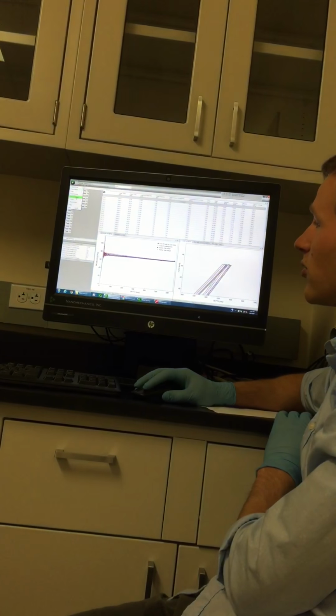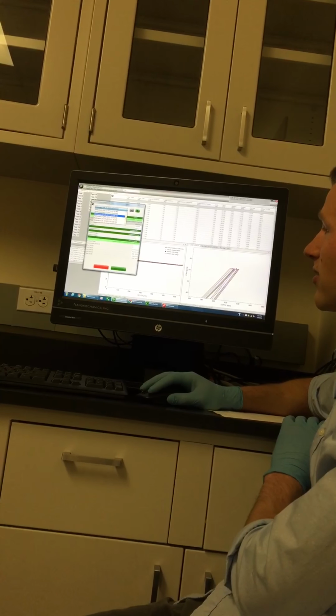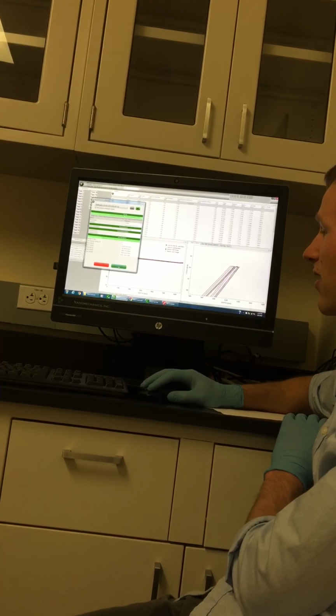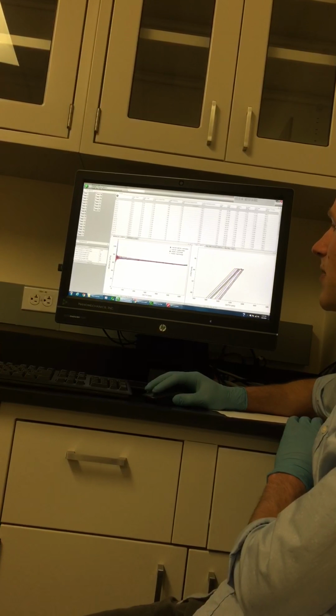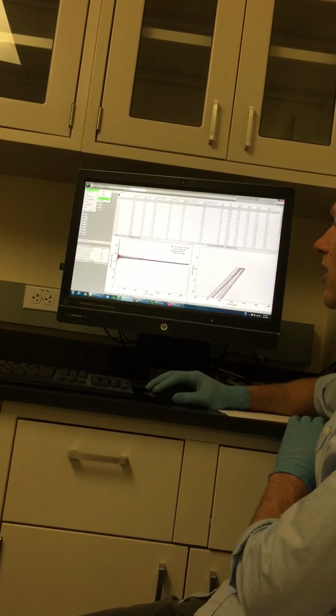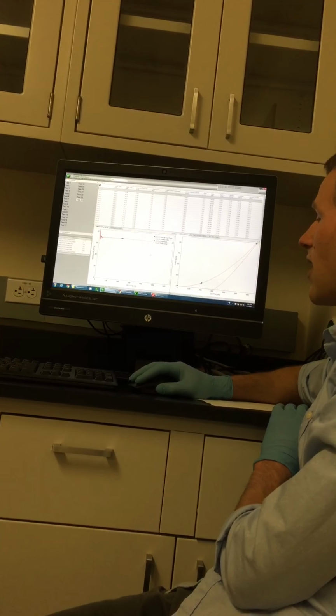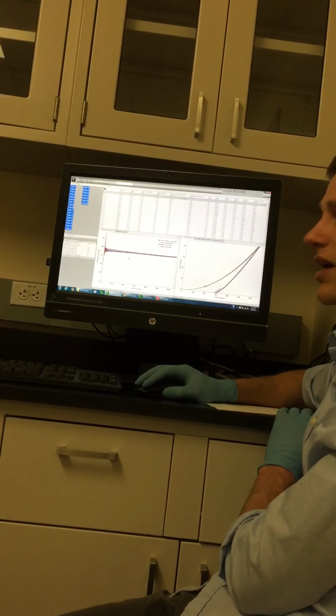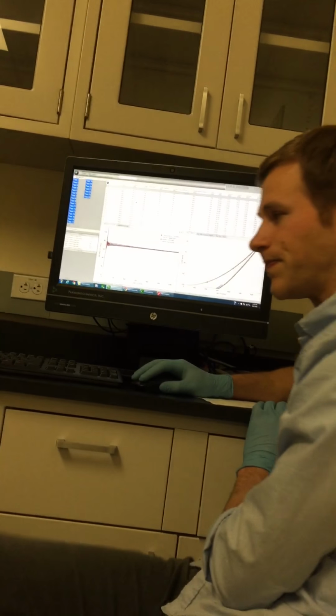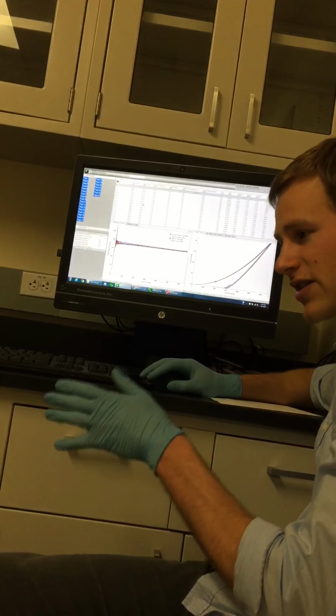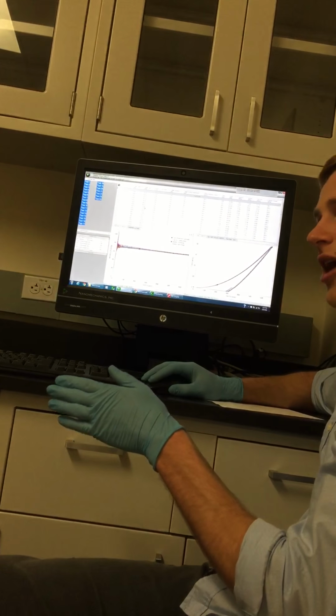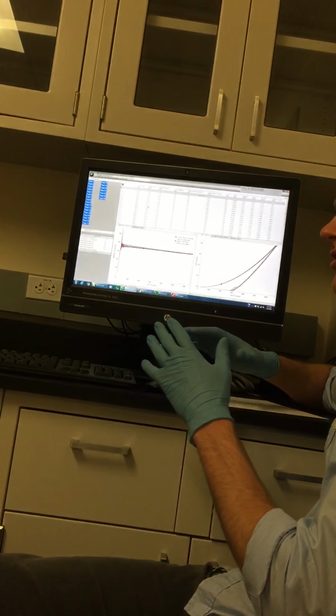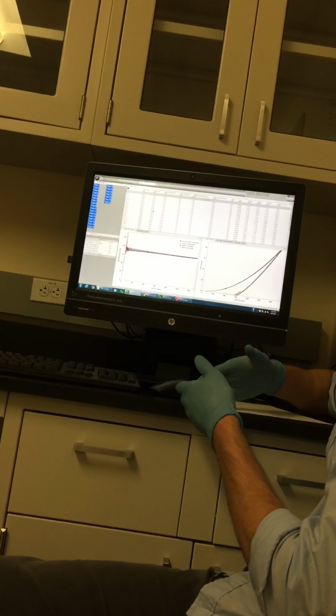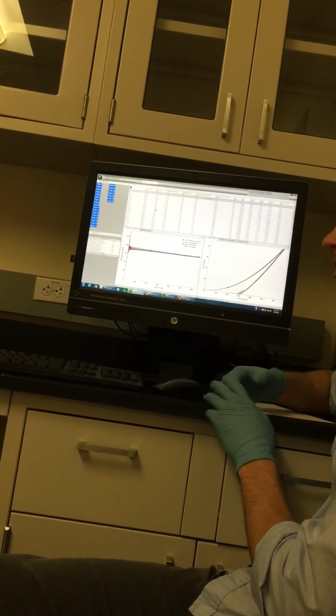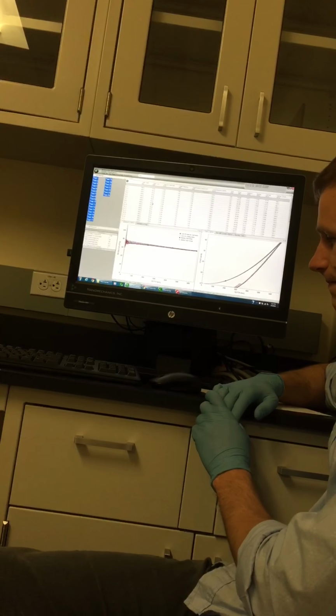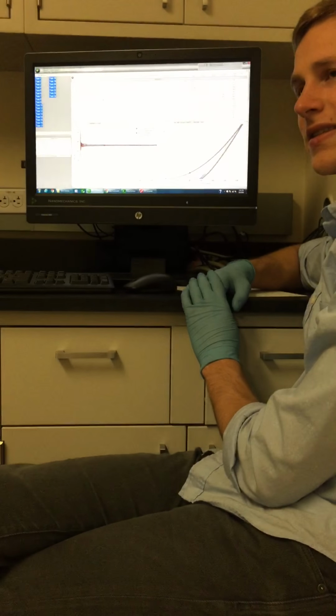And so you do that by changing the tip here. Say I want this one instead, and I would hit accept or save and close. And then you could go up to sample data and recalculate. It would recalculate everything, and then the data would look slightly different because it had a slightly different calibration. Because the assumption that would be changing would be a slightly different tip shape, or a slightly different cross-sectional area as a function of contact depth is really the thing. So that's the calibration. Do you have any questions?